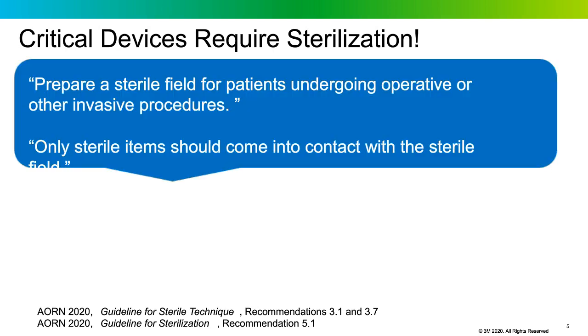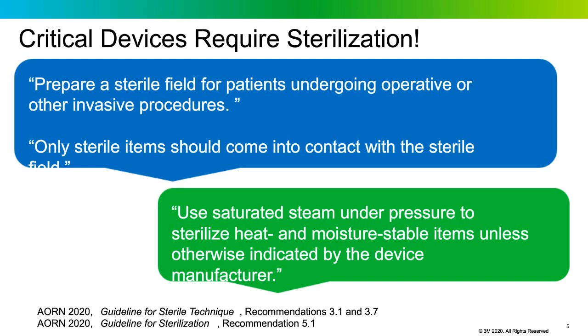From the Spaulding classification scheme, which classifies items based on their intended use, critical devices are defined as instruments that enter sterile tissue, including the vascular system. Reusable critical devices should be cleaned and sterilized between patients because the sterilization process destroys all living organisms, including bacterial spores. The AORN guidelines state that only sterile items should come in contact with the sterile field, and that saturated steam is the preferred sterilant for heat and moisture-stable items unless the device manufacturer's IFU states otherwise.